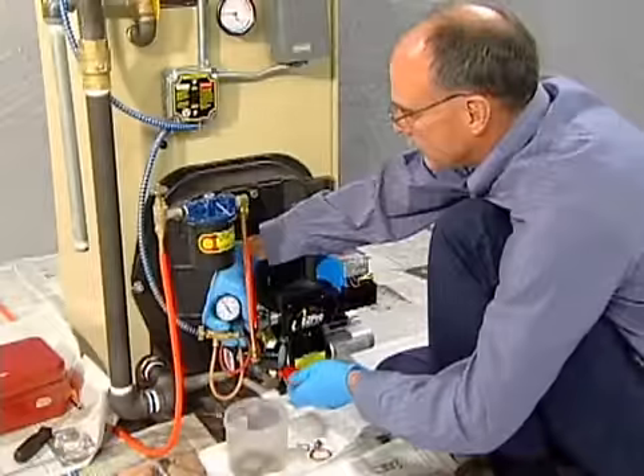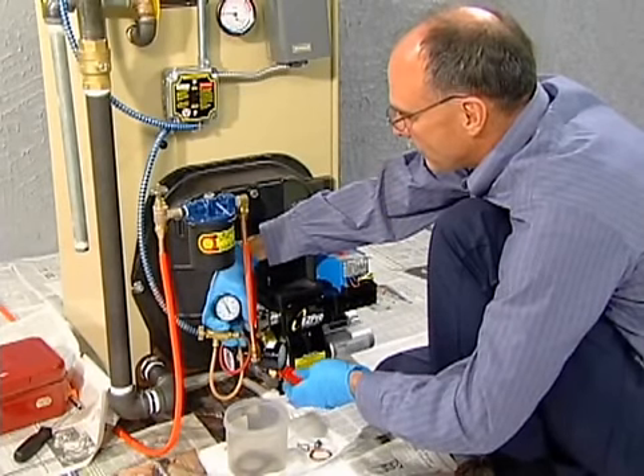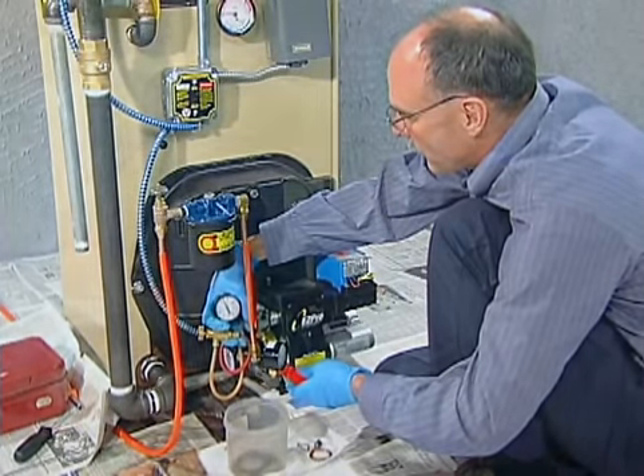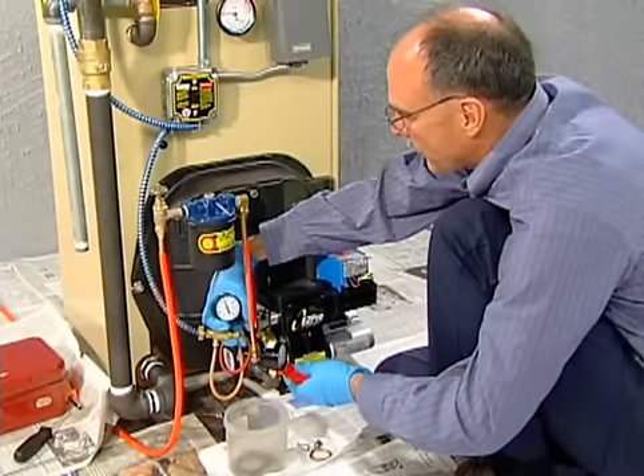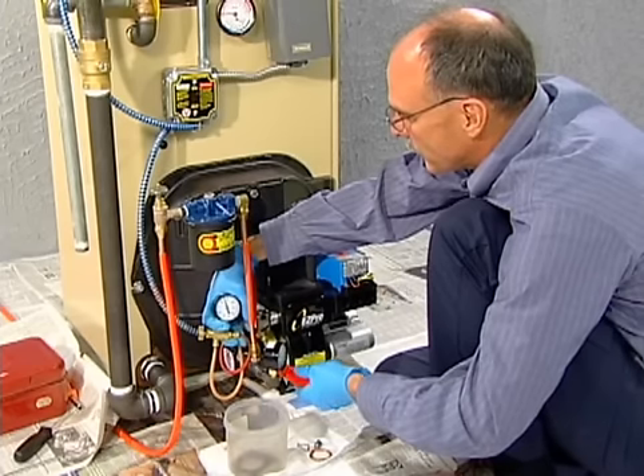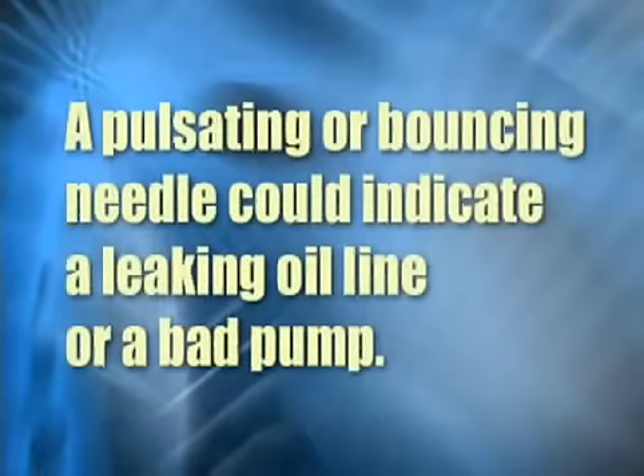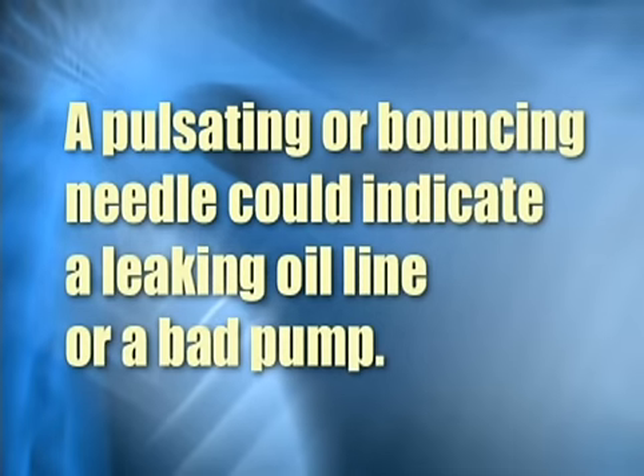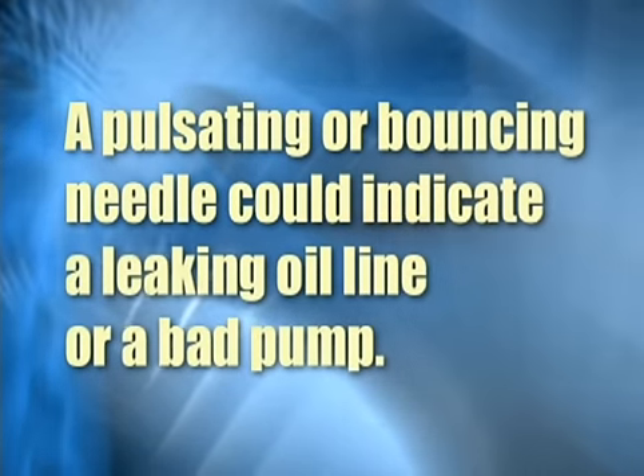Operate the unit and increase the pressure 40 to 50 psi above the recommended setting, not exceeding 200 psi. Check that the pressure reading changes smoothly as you turn the adjustment screw. A pulsating or bouncing needle could indicate a leaking oil line or a bad pump.